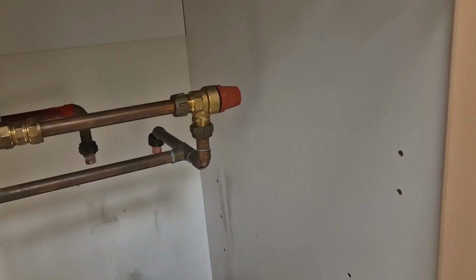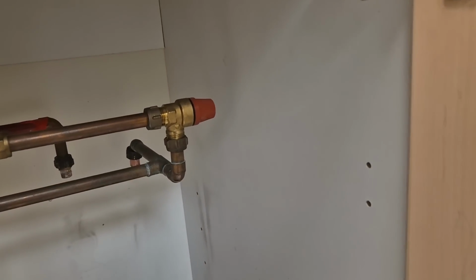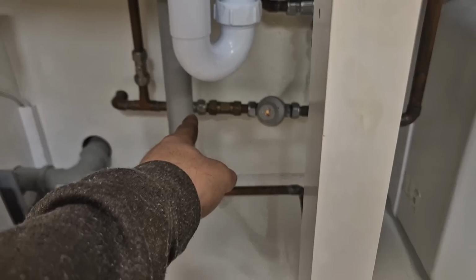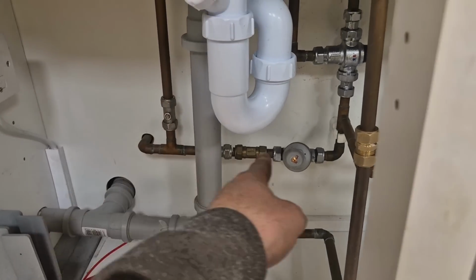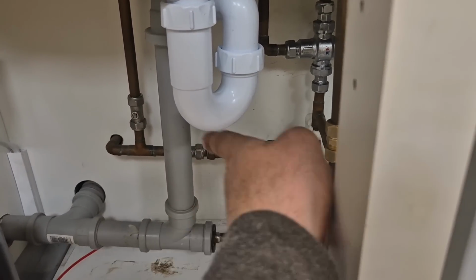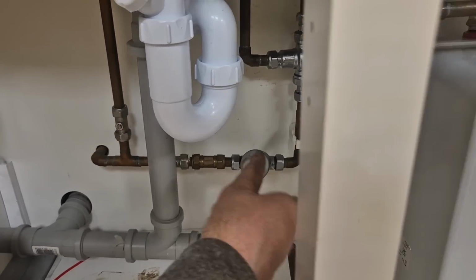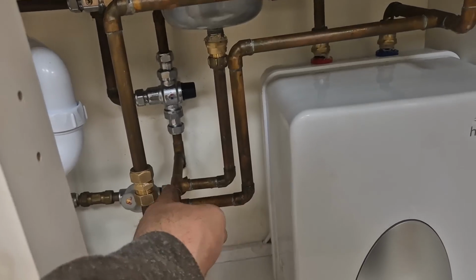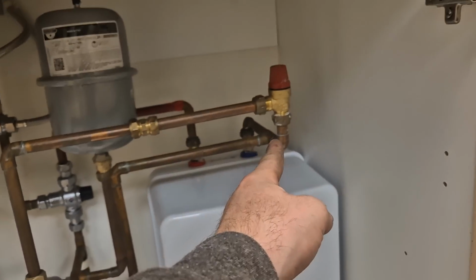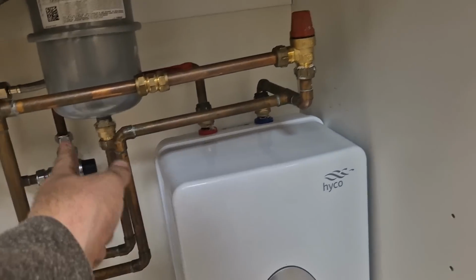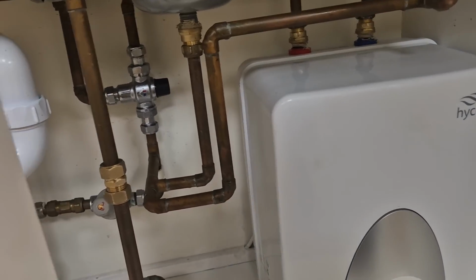Seen it all. To be honest, it's not the first time I've seen them. People put them on the wrong way around. So on this, we've got nearest cold draw off, isolation point, check valve to stop any hot water going back. That's fluid cat 2. 3-bar pressure reduction valve into the heater, 6-bar PRV, and then out through the hot, and then the blender. So it is plumbed correctly.